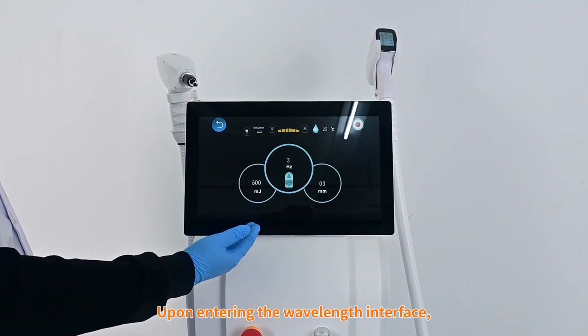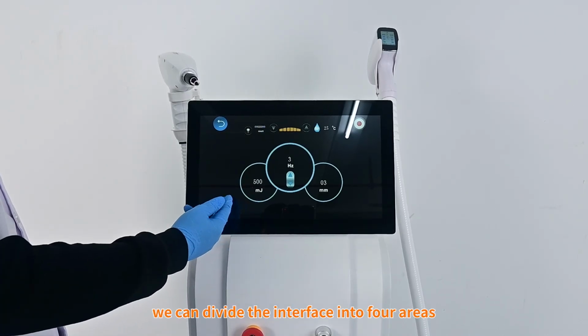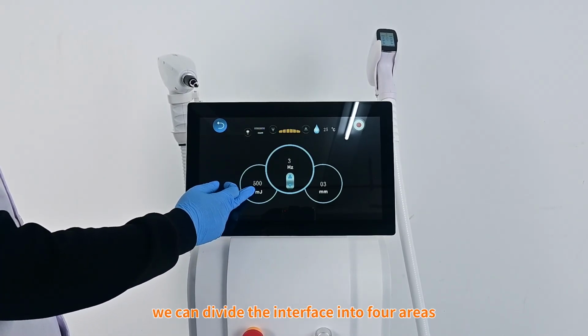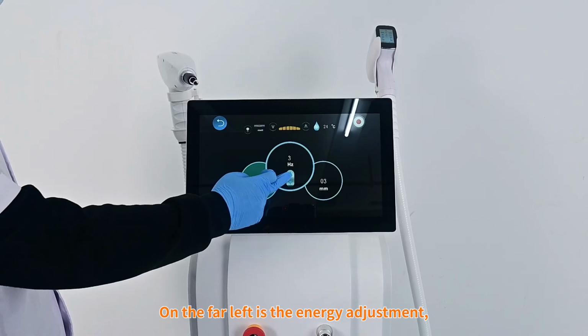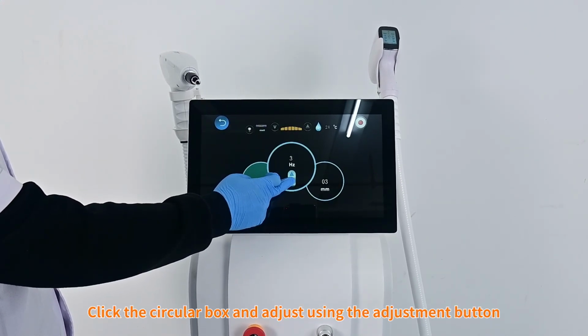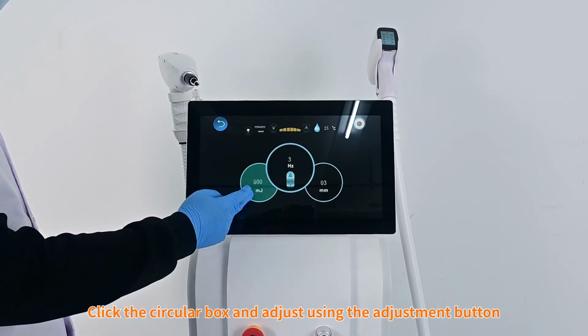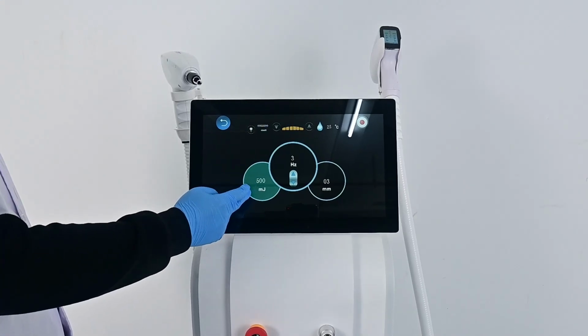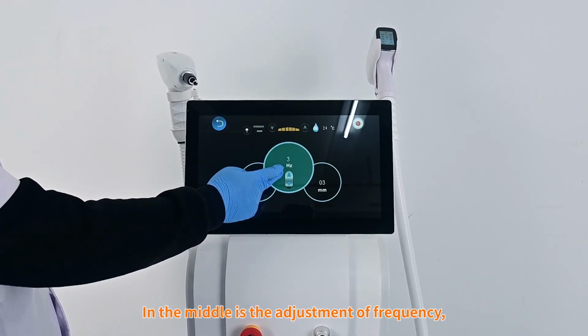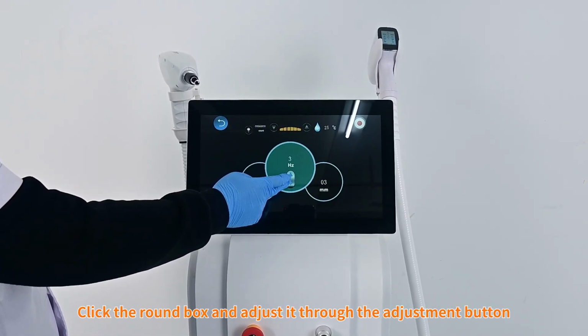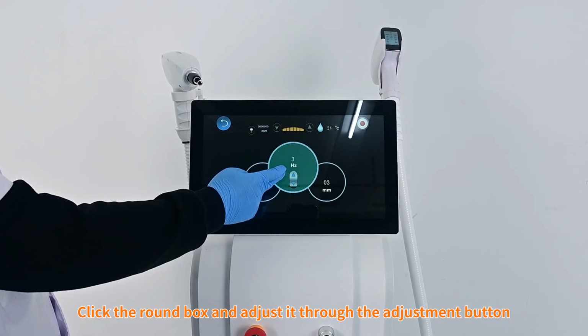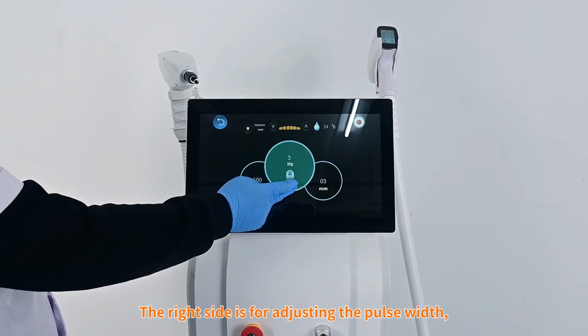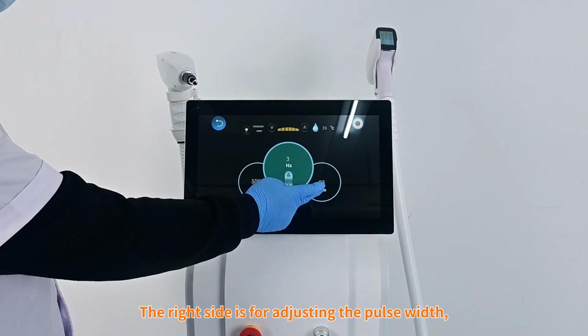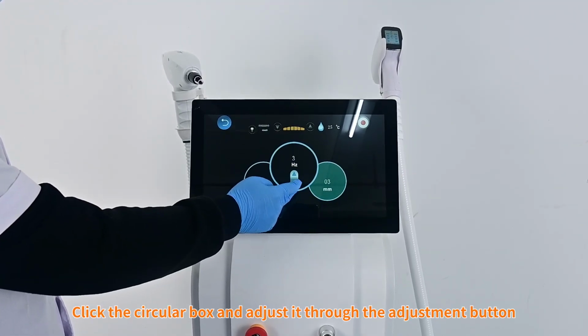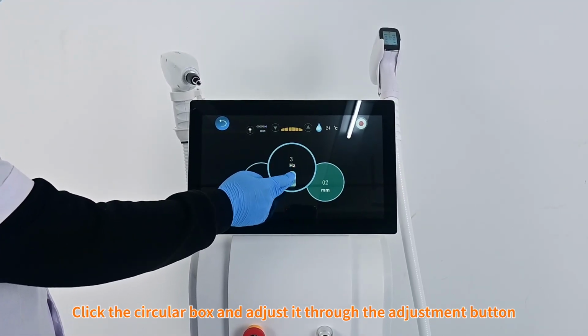Upon entering the wavelength interface, we can divide the interface into 4 areas. On the far left is the energy adjustment. Click the circular box and adjust using the adjustment button. In the middle is the adjustment of frequency. Click the round box and adjust it through the adjustment button. The right side is for adjusting the pulse width. Click the circular box and adjust it through the adjustment button.